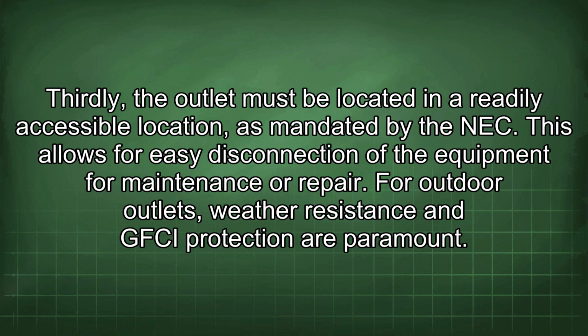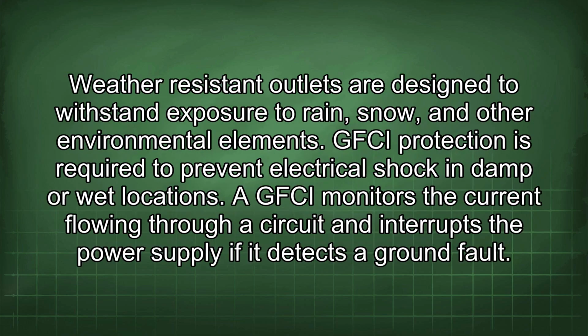For outdoor outlets, weather resistance and GFCI protection are paramount. Weather-resistant outlets are designed to withstand exposure to rain, snow, and other environmental elements. GFCI protection is required to prevent electrical shock in damp or wet locations. A GFCI monitors the current flowing through a circuit and interrupts the power supply if it detects a ground fault.